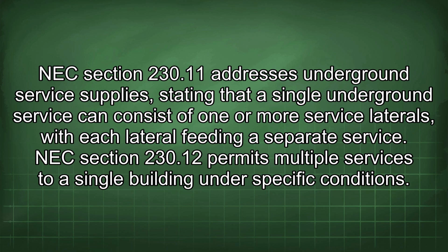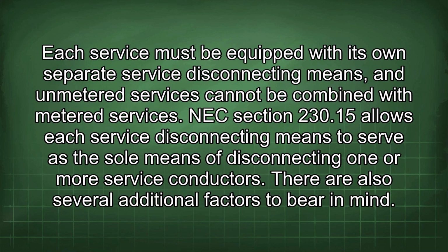NEC Section 230.12 permits multiple services to a single building under specific conditions. Each service must be equipped with its own separate service disconnecting means, and unmetered services cannot be combined with metered services. NEC Section 230.15 allows each service disconnecting means to serve as the sole means of disconnecting one or more service conductors. There are also several additional factors to bear in mind.